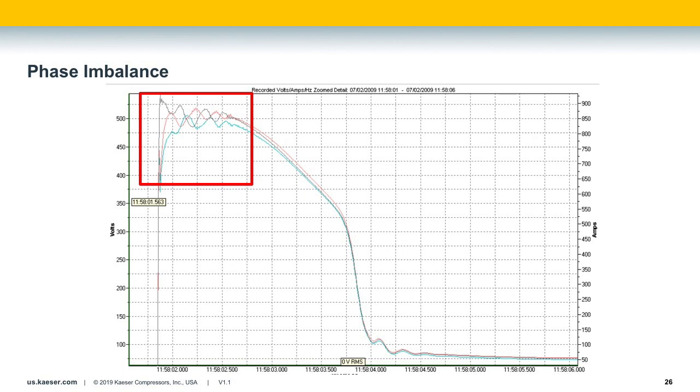They took this information to the breaker manufacturer, and the result was the electronic inverse time delay breaker was calculating this as a leak to ground, even though it really was not. As a test, the ground fault was disabled on the breaker and the unit was able to start without problems. The facility had to turn off the ground fault portion of the breaker and redo the electrical installation to make it meet code.